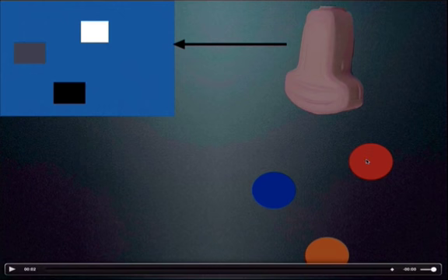You can see the red signal here is a bright reflector, and it's also closer to the probe. Well, the time that it took for the signal to return there was the shortest, and we know that it returned to this location of the probe.